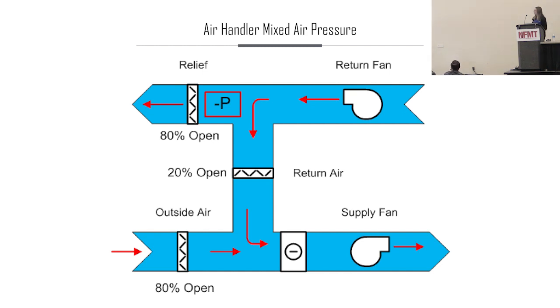Without that, what we really ran into was we had a system where we measured and there was negative pressure at the relief damper. And the result of negative pressure at the relief damper is the system was then trying to pull any outside air this direction, and we were actually not getting the outside air we needed into the building. That was diagnosed by just running around pulling pressures on the system and going, wait a minute, that doesn't make sense. So just a little vignette, again, using static pressure measurements on the air side as a diagnostic tool to ask, are we expecting the right pressures at the right places along the pathway?